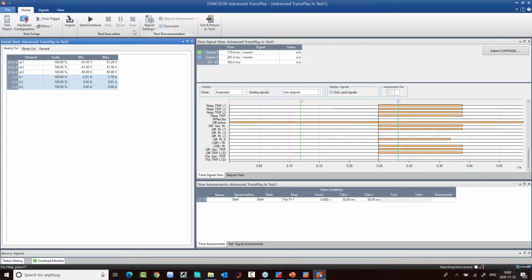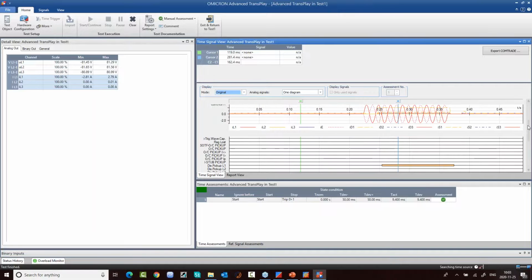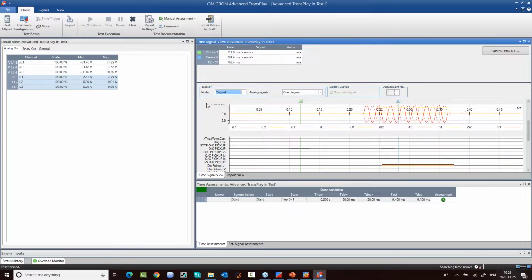If I start it again, for sure, no difference, and I found that the relay has differential protection active. That's why this is a type of differential, not zone 1, but no problem. The philosophy here is to check a kind of fault, not only a certain fault. As you will see here, the 2 binary outputs are already activated as per our configuration. This is started from here to there as we assigned, and this is started from here to there as the digital input. This is for the binary signal.